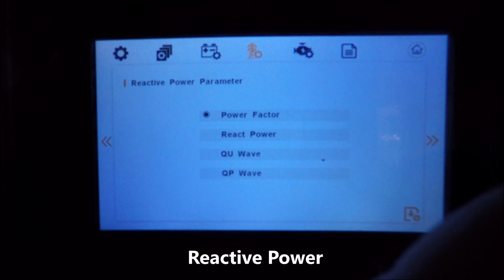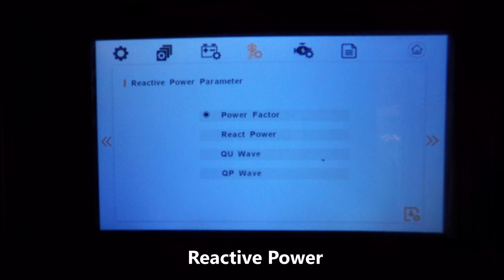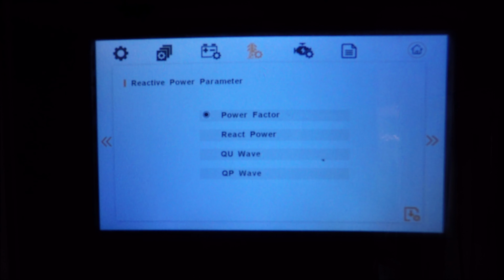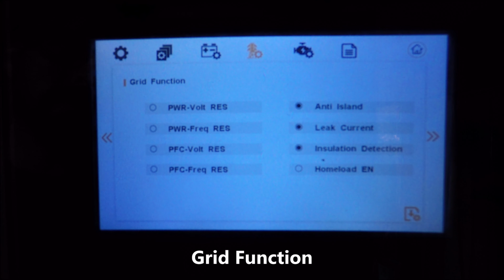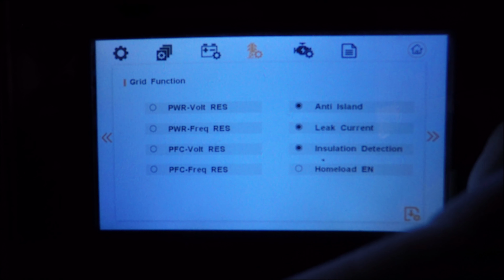You may again have different rules for the grid standard where you are. This allows you to make additional settings. Reactive power, we have the reactive power parameter. This depends on the country where you are and which country is selected, if required by their grid. You want to just keep it on power factor if you're in the United States and accept the default. Grid function, accept the defaults unless there's a specific use case and you've been told to change it. You do want anti-islanding, you want to detect leaking current, and you want insulation detection.